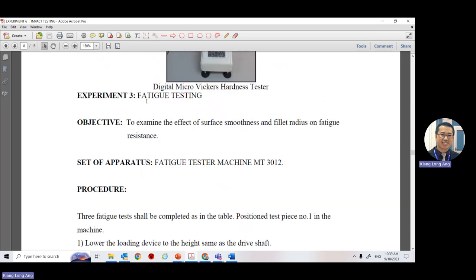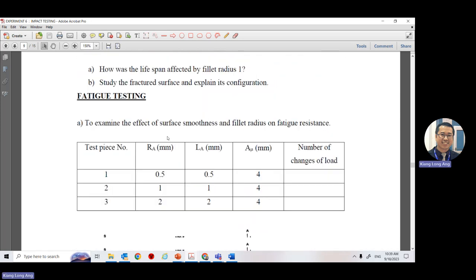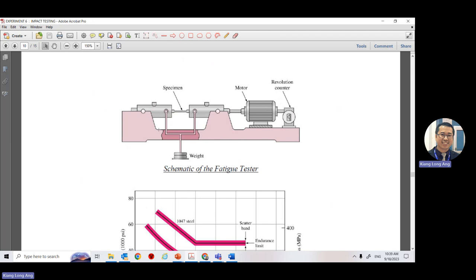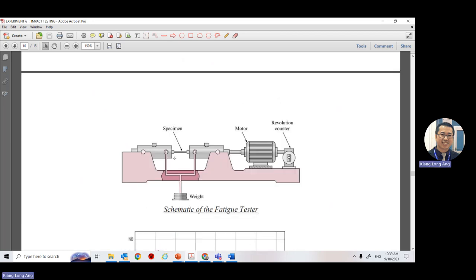The third experiment is the effective (fatigue) testing machine. You will see this machine this Wednesday. You need to dismount something here — you need to remove a part and put in the sample, dismantle the grip, insert the sample, then mount and screw it back. Record likewise. Once everything is secured, try to turn — if it cannot turn, it is set properly.